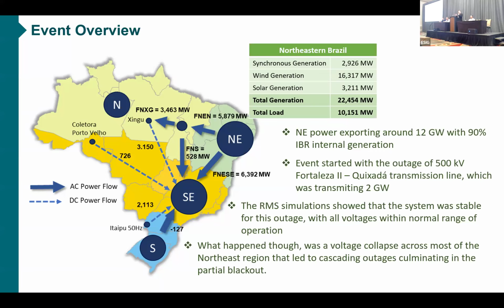As I mentioned, we've had 20% average IBR penetration in Brazil in 2023, but it's really concentrated in the Northeast. At the time of this event, this region had 90% IBR internal generation. The event started with the outage of a transmission line, transmitting 2 gigawatts, located at the north part of the northeastern region, right around here.